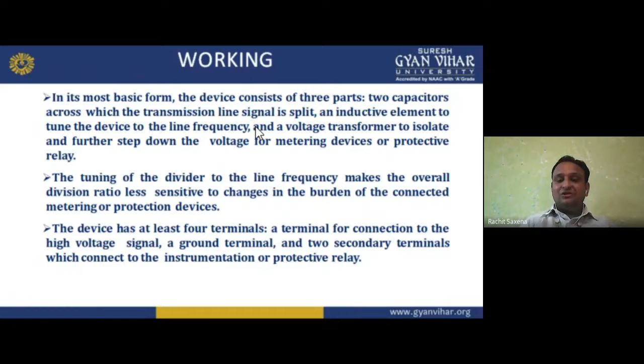The tuning of the divider to the line frequency makes the overall division ratio less sensitive to change in the burden of the connected metering or protection. So it is less sensitive to the change in burden. Okay, so no changes when the burden is different, meaning the load is different in metering. The device has at least four terminals: a terminal for connection to the high voltage signal, a ground terminal, and two secondary terminals, which are connected to the instrument or protective relay. So four terminals we have.